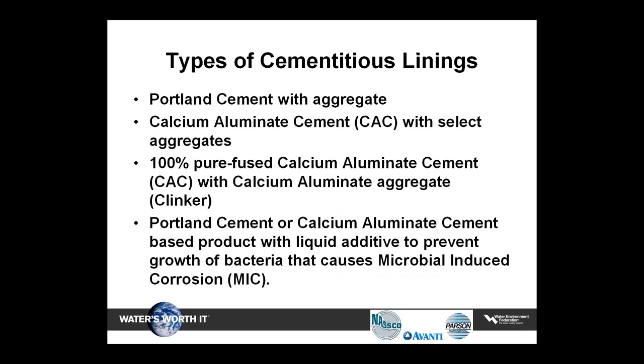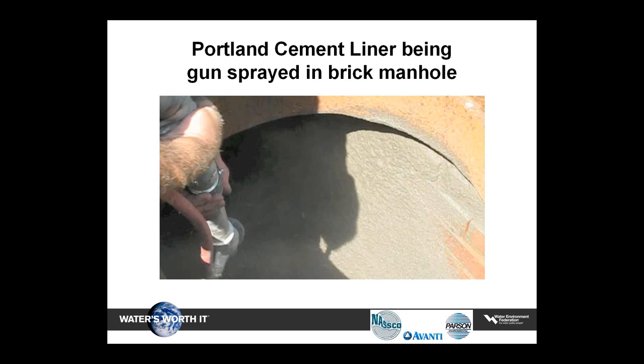Common types of these products include Portland cement with aggregate (typically fine grain sand), calcium aluminate cement with select aggregate, calcium aluminate cement with calcium aluminate aggregate (referred to as clinker, a byproduct from processing calcium aluminate cement), and Portland or calcium aluminate cement-based products with a liquid additive to prevent growth of bacteria that causes microbial induced corrosion (MIC). Portland cement-based products usually exhibit the longest working times, can be applied at a thicker rate per coat, and have the highest 28-day compressive strengths. They may be the most commonly utilized cementitious linings due to lower cost, acceptable corrosion resistance, and user-friendly application.